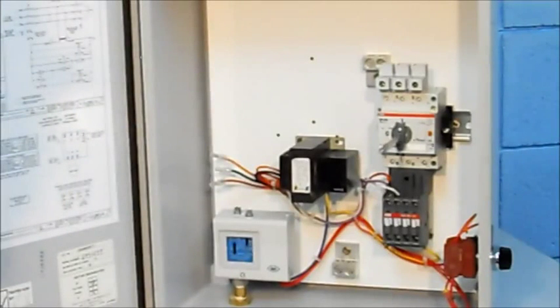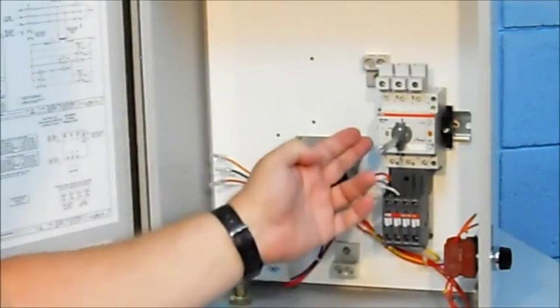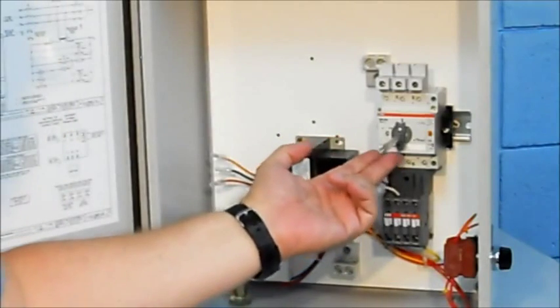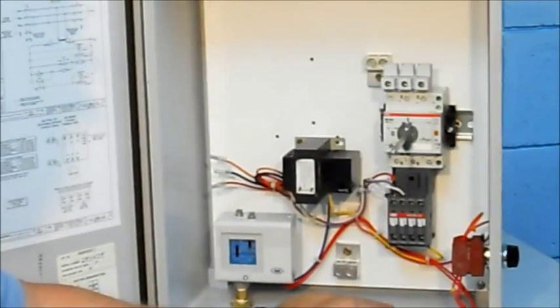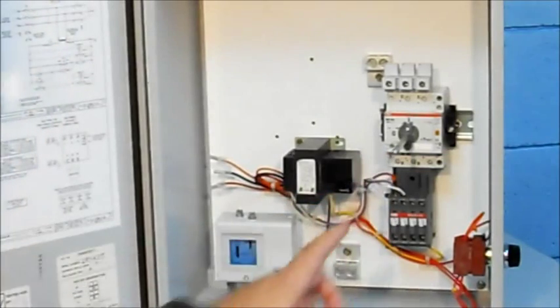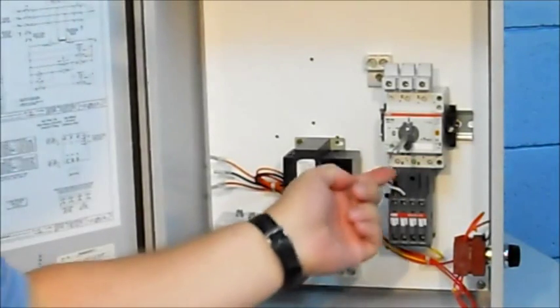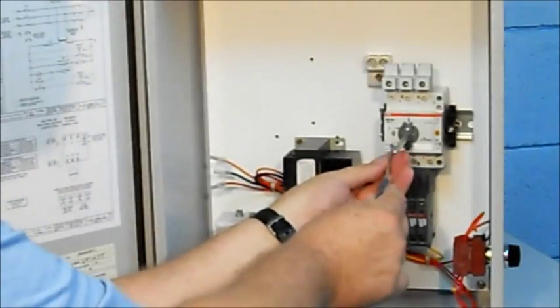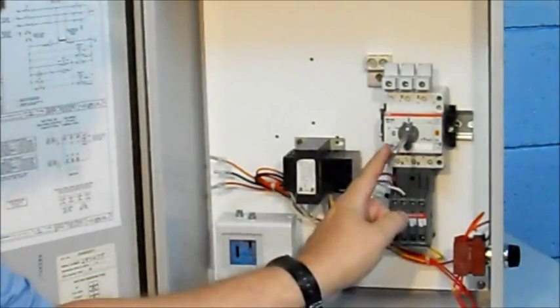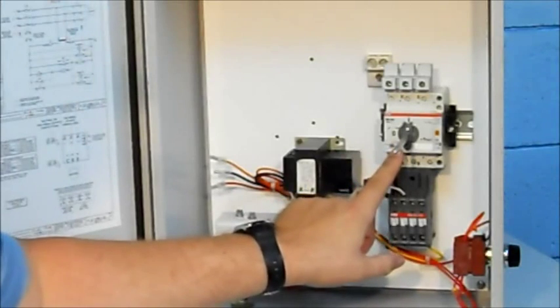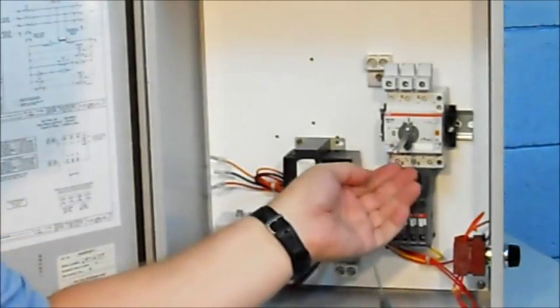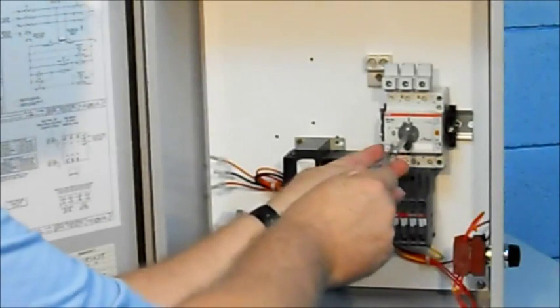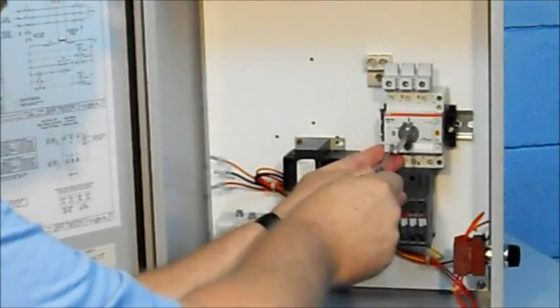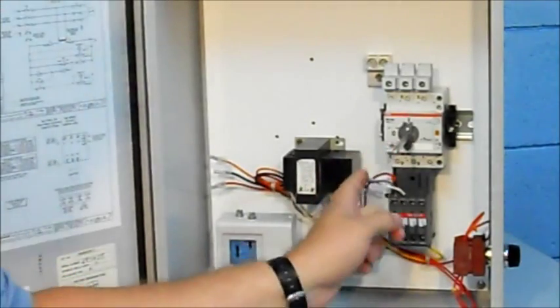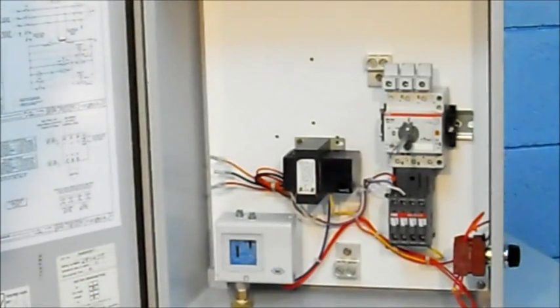One other thing to consider is if the disconnect switch trips, it may be due to an adjustment on the disconnect switch itself. You'll find a small adjusting area here with numbers around the dial. These numbers correspond to the full load current of your motor. You want to select the full load current rating based on your motor nameplate, and that will be the overcurrent trip position that you would use for that particular unit.